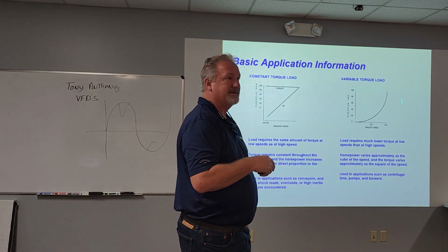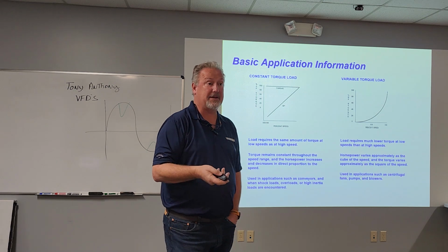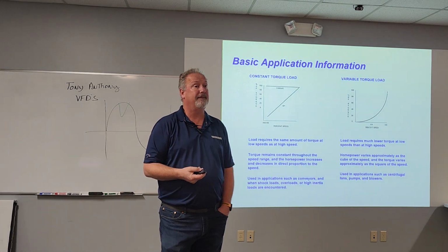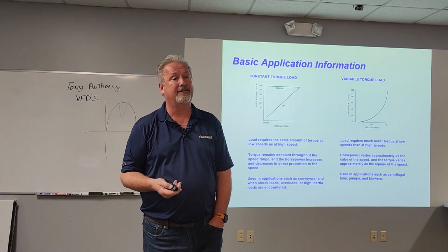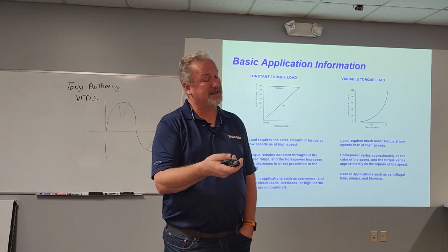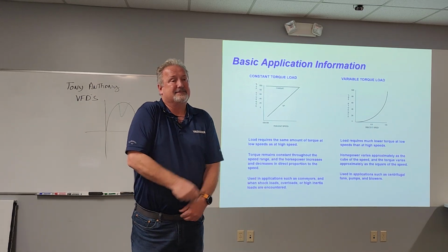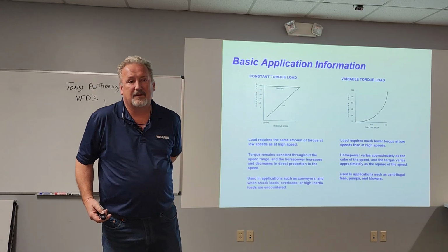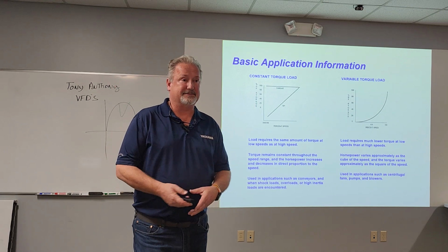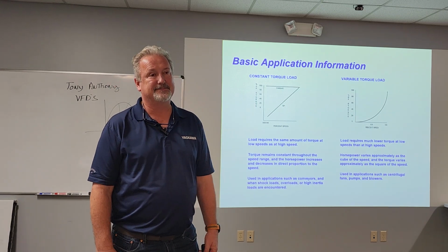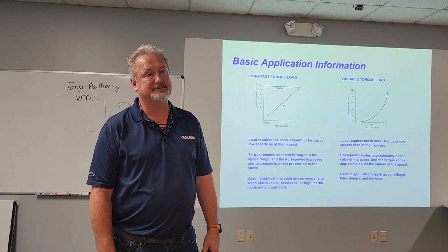If you can slow it down, which in most applications you can. Out there with ductwork and stuff not being sized right, trying to carry static pressure, they've got problems with pumps or piping not being right. We can't maintain a differential. I mean, I know guys that are amping out their motors and running their VFDs at 80% instead of 60.